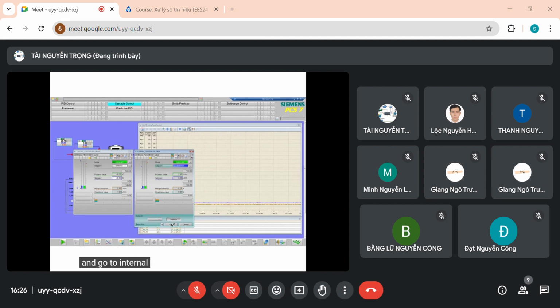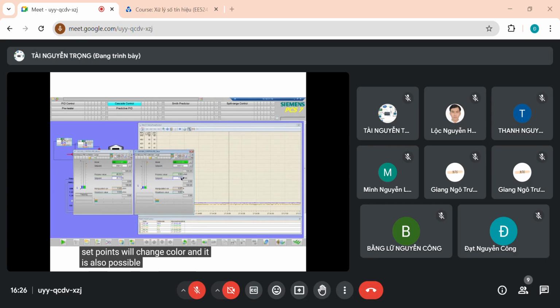So what we can do now is change and go to internal set point mode, and you will see here that the set point will change color, and it is also possible now to go, for instance, to a set point of 5 liters per minute. Okay, so we are in internal set point. So this means now that the link between the manipulated value of this controller and the set point of this controller has been broken. Okay, we will see when we talk about cascade control that you have to do something about this controller. If you do nothing, you will see that there will be a wind up of the integral action.